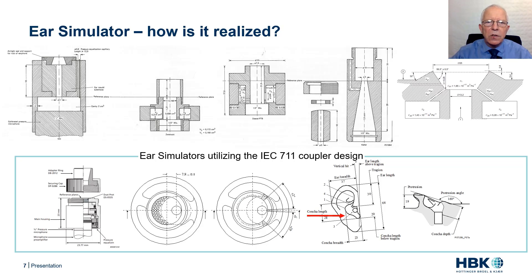A human-shaped pinna with a cylindrical shaped ear canal is shown on the slide. With a 711 coupler attached to the pinna simulator, it forms the Type 3.3 ear simulator. This ear simulator has been in use since the late 1980s.